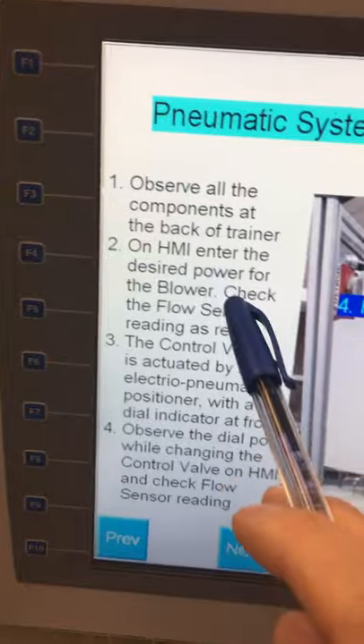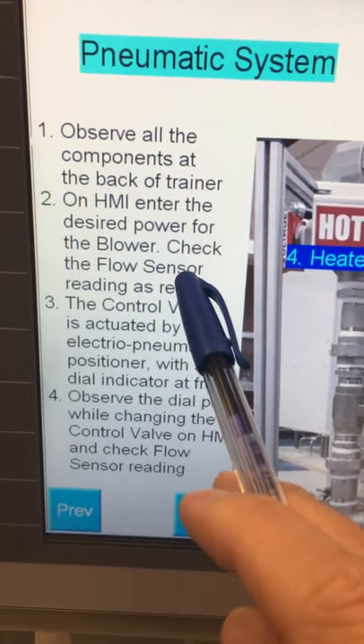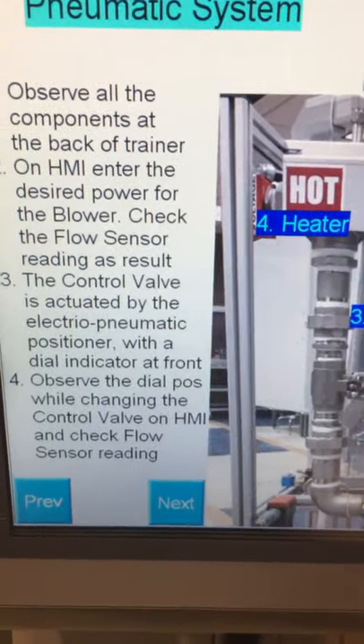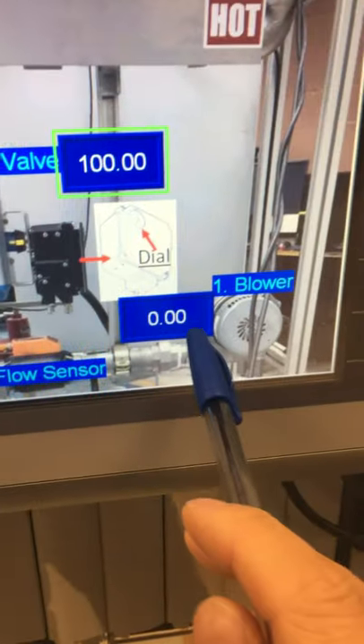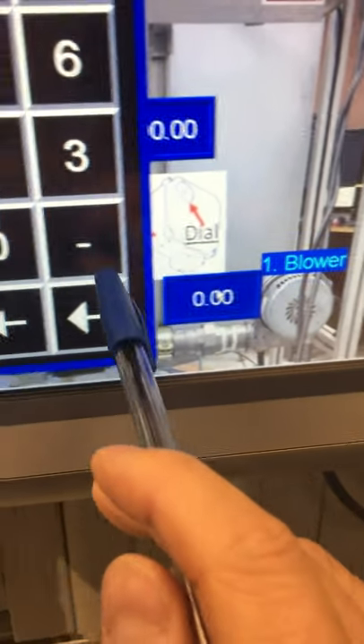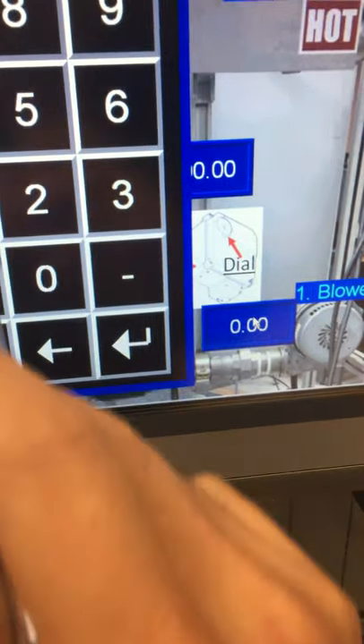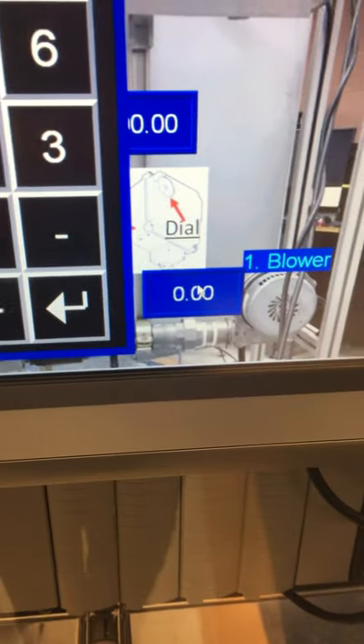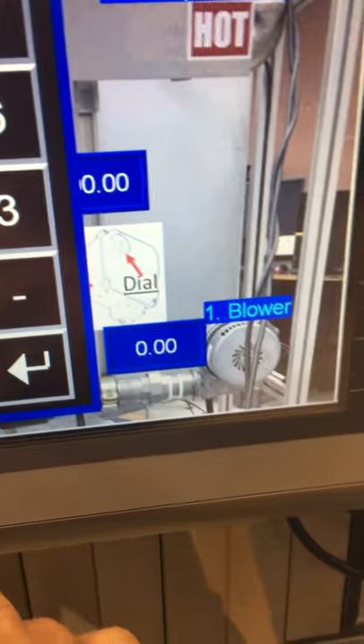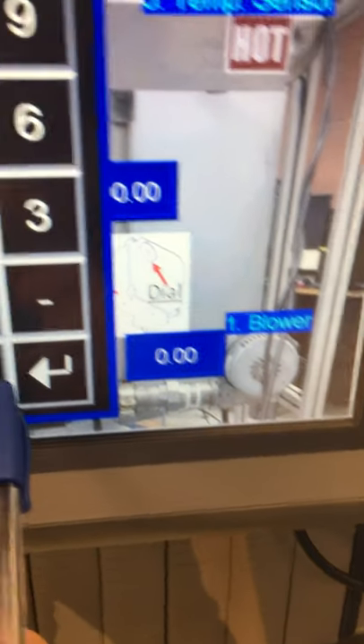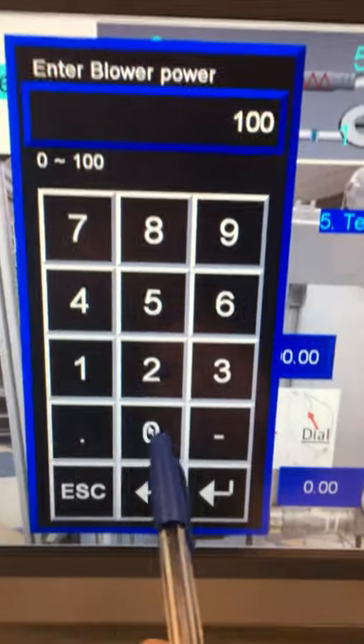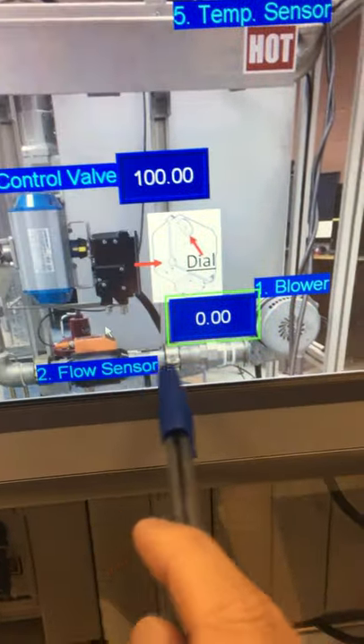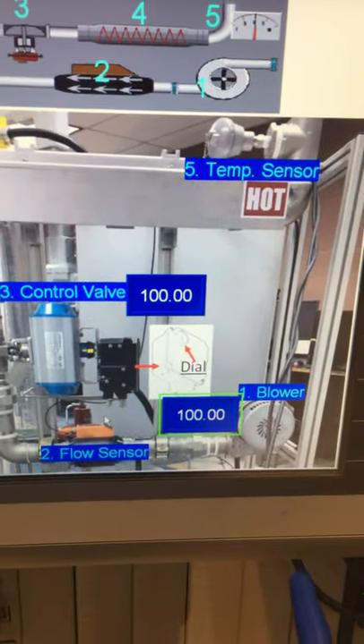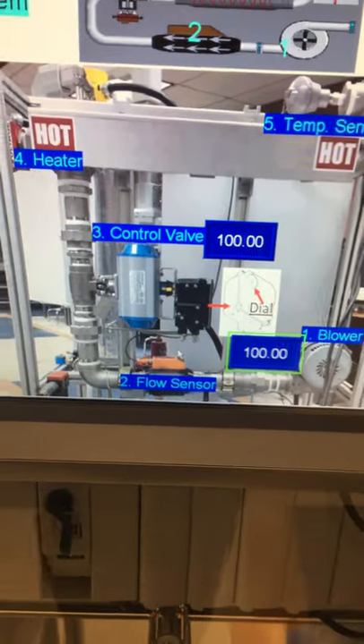Number two, on the HMI, enter the desired power for the blower and check the flow sensor reading as a result. Right now, the blower is working at 0%, and you may notice the flow sensor reading is 0. I'll change the blower to 100% and press enter. You hear the noise. Now the blower is working at 100%.